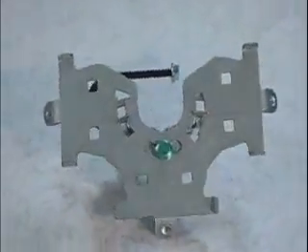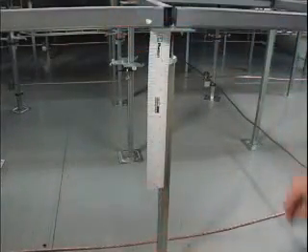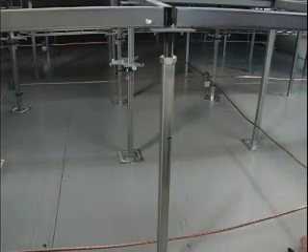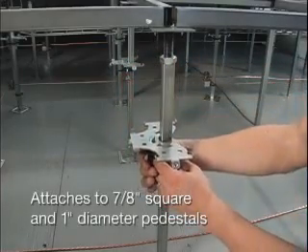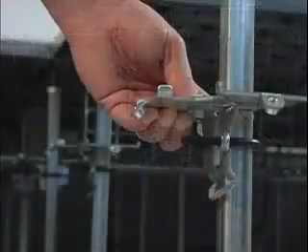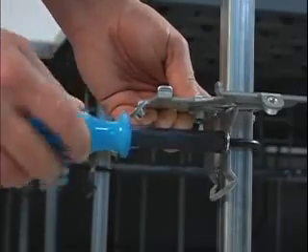Wire basket sections are attached to and supported by the floor pedestals and the innovative pedestal support brackets. The brackets utilize a unique clamping mechanism that secures it to the pedestal while creating an electrical bond between it and the pedestal. This mechanism consists of a swinging U-bolt and a captured nut. The bracket can be positioned anywhere along the pedestal, providing additional flexibility when routing the system at various levels. Once positioned, the U-bolt is wrapped around the pedestal and the nut is tightened until the bracket is set, requiring only a simple 7/16-inch nut driver to complete the assembly.